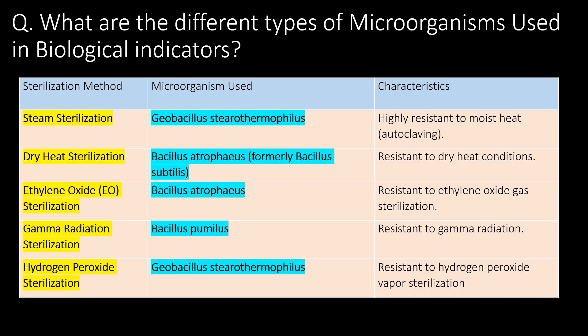Very important question: what are the different types of microorganisms used in biological indicators? Referring to a table for various sterilization methods, microorganisms commonly used as biological indicators and their characteristics: for steam sterilization, dry heat sterilization, ethylene oxide sterilization, gamma radiation sterilization, and hydrogen peroxide sterilization, we use Geobacillus and Bacillus species as biological indicators, due to their resistance toward those particular sterilization methods.